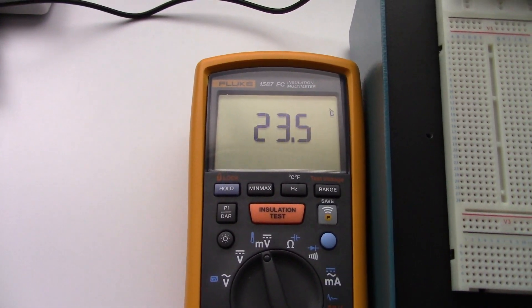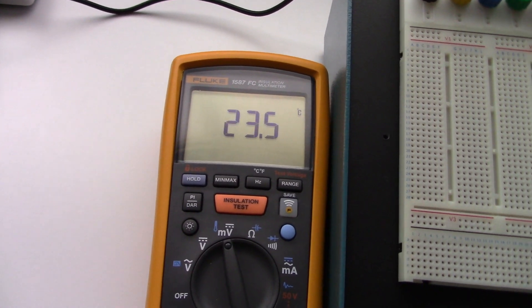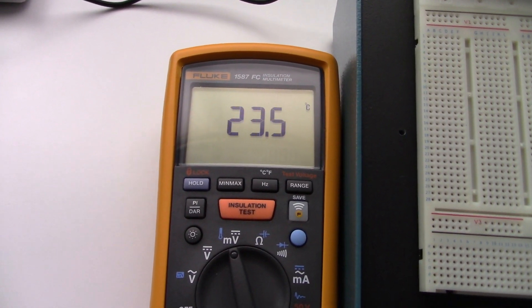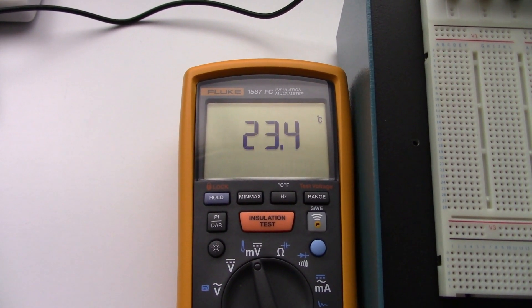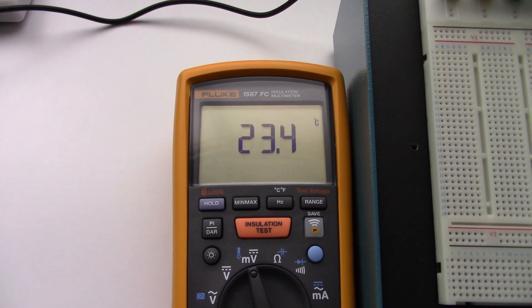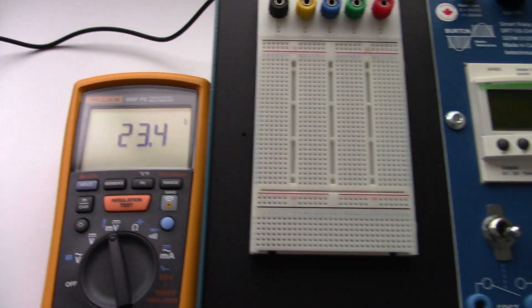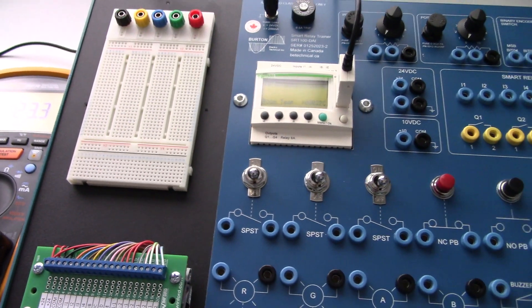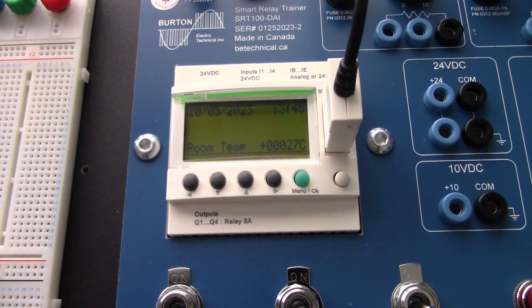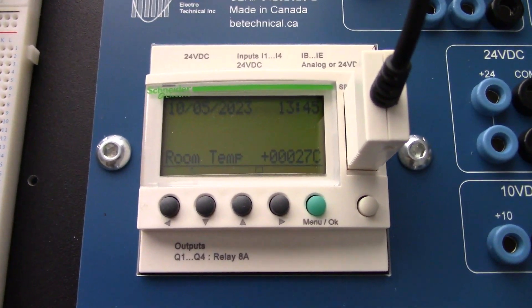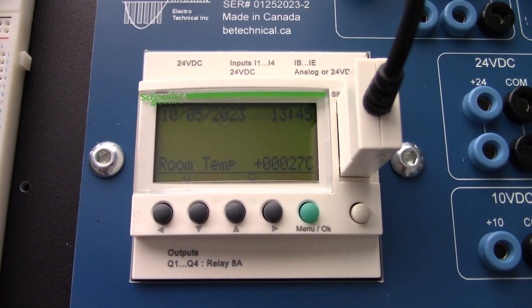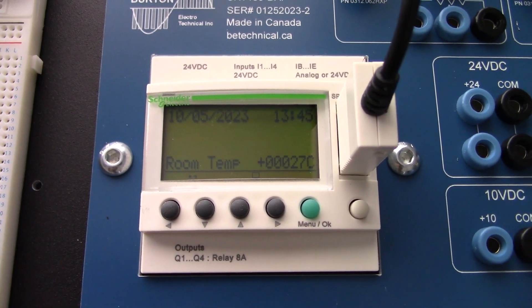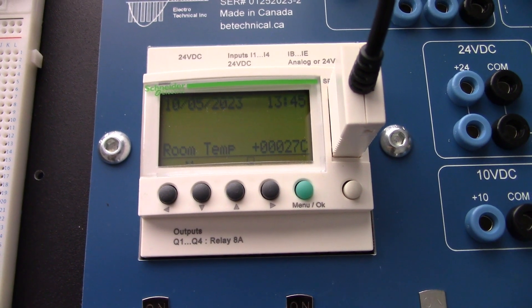The meter is reading around 23.5 degrees Celsius. Over on this side, on our controller, we are reading 27. So we've got a little bit of an offset that we need to put in. What I'll do is I'll go in and adjust that block, that calibration block.